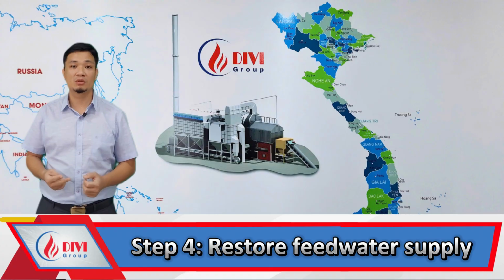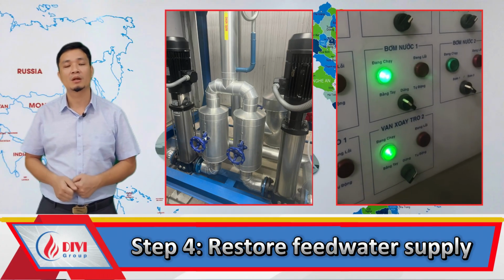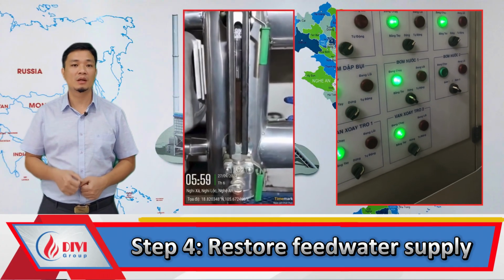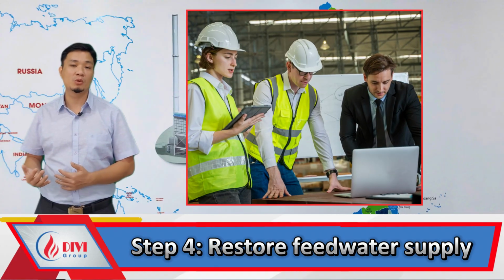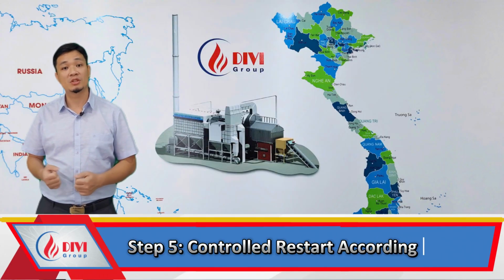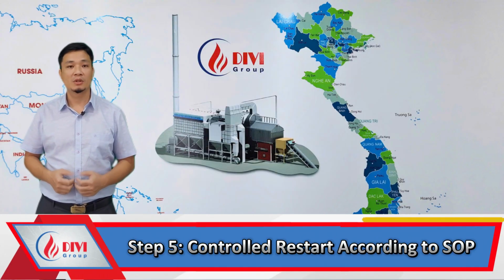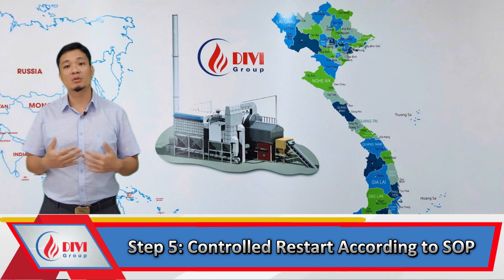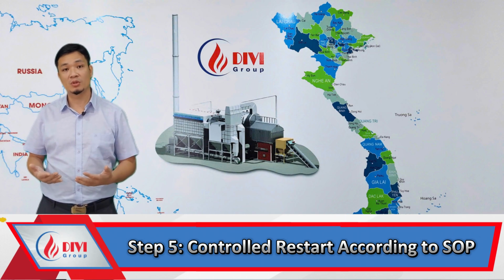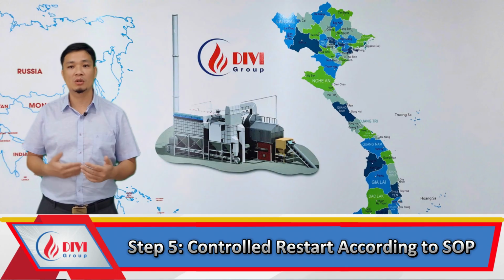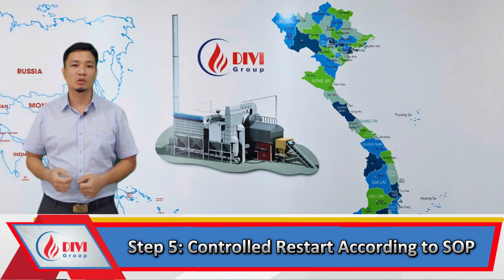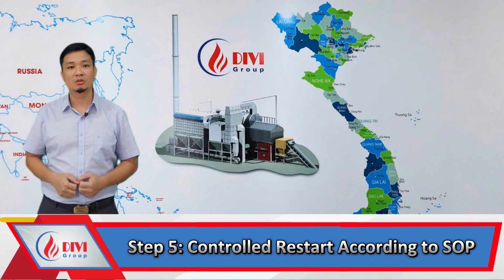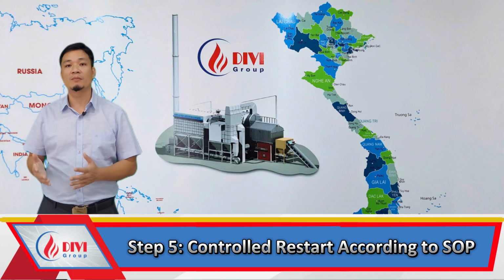Switch to manual mode and feed water gradually while monitoring the sight glass closely. Management approval is required before proceeding. Controlled restart. According to SOP, ensure the water level is within the safe operating range before reigniting the boiler. Follow your plant's official startup procedure or refer to our video, 3 steps to safely start a boiler.